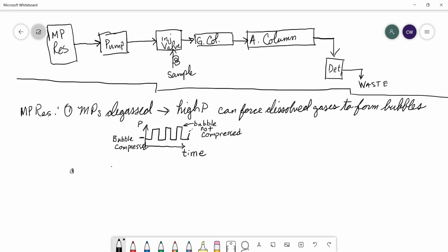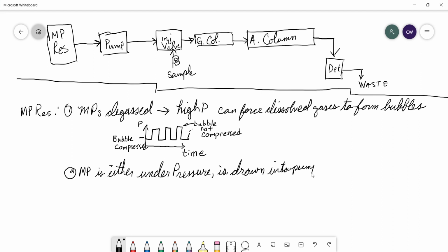Okay? The other thing is, all right, we have to make sure that the mobile phase is either under pressure or in some way is drawn into the pump without gas. Okay? We need to make sure that that mobile phase does not develop any air bubbles in the pump. All right? Because that will cause this same problem, right? The pressure will drop and then it will go up, and then it will drop and then it will go up.